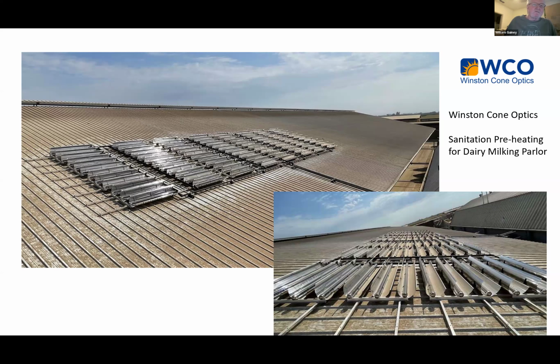The other advantage we have is we can operate at a higher temperature than an electric water heater, and we can provide more bacteria reduction in their piping and their heat exchangers. Dairies get paid by the quality of their milk, so the fewer contaminants and bacteria in their milk, the higher the value. If solar thermal can purge their piping and heat exchangers of this bacteria with higher temperatures, obviously the farmer is going to benefit from cleaner, more healthy milk and a healthier herd.